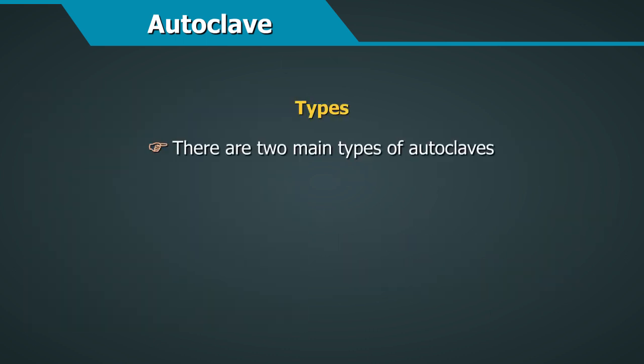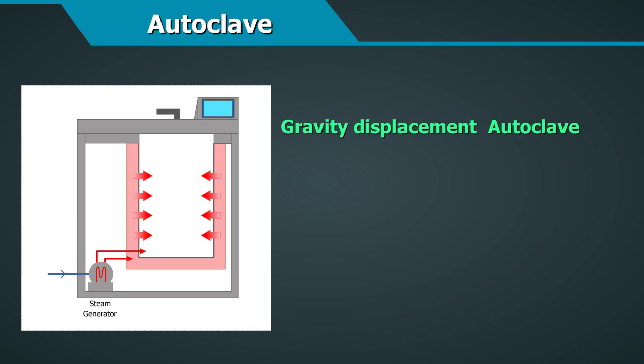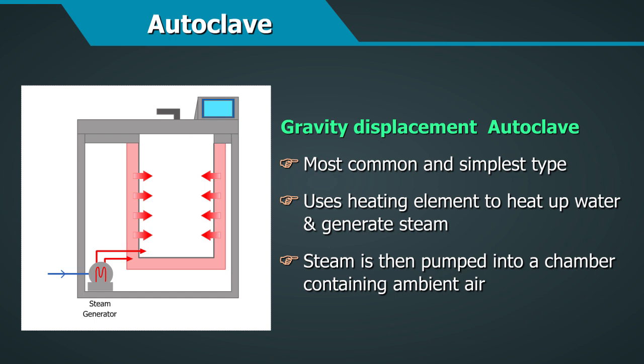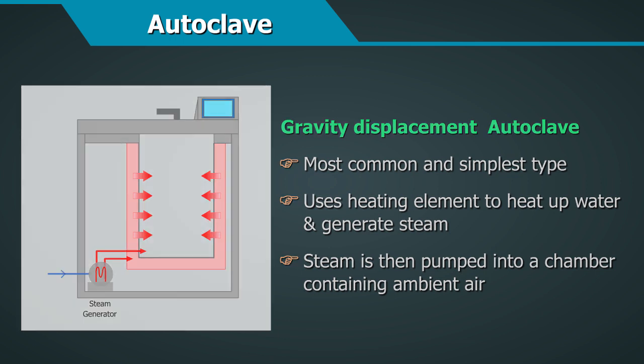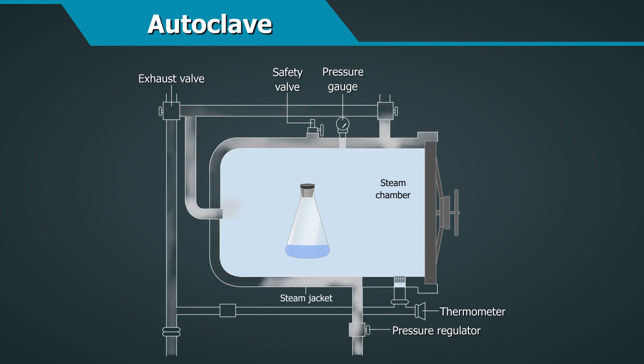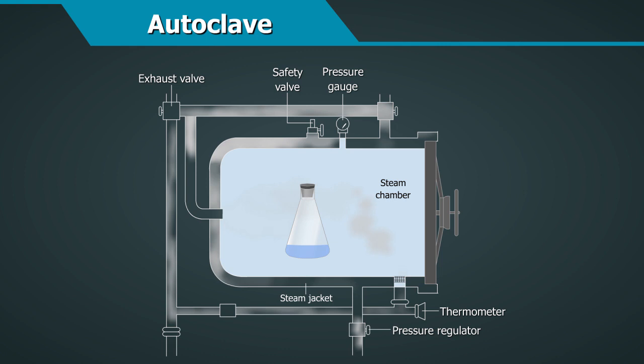There are two main types of autoclaves. The gravity displacement autoclave is the most common and simplest type. It uses a heating element to heat up the water and generate steam. The steam is pumped into a chamber containing ambient air, and due to its lower density, it rises to the top and gradually displaces all ambient air, which is forced out through a vent below. Steam continues to be pumped at higher pressure, reaching a temperature of about 121 to 140 degrees centigrade. After the cycle, steam is discharged through the exhaust valve.